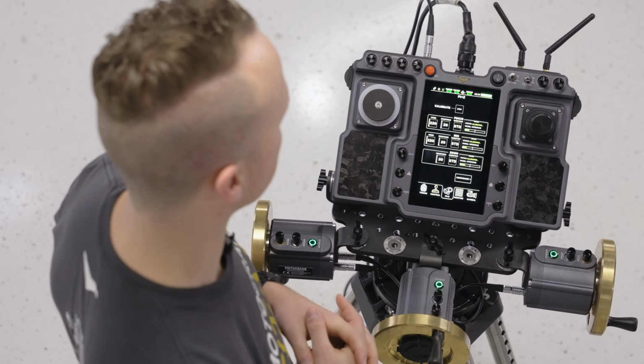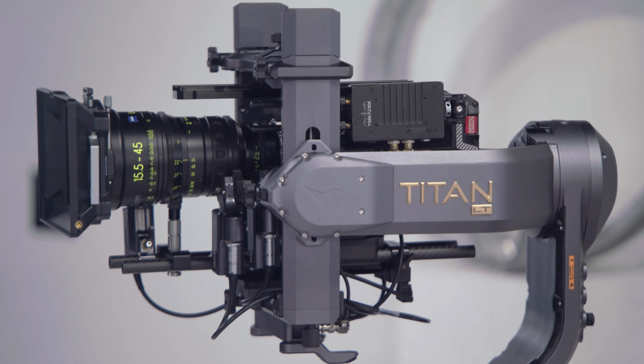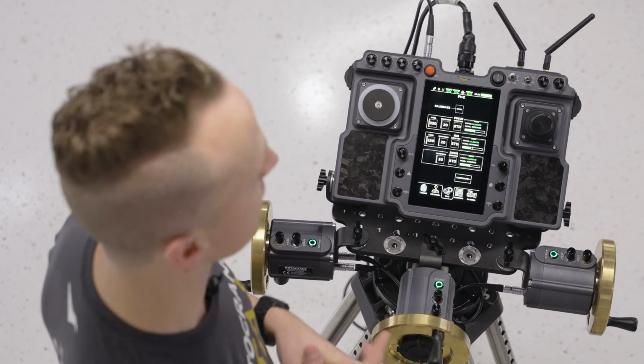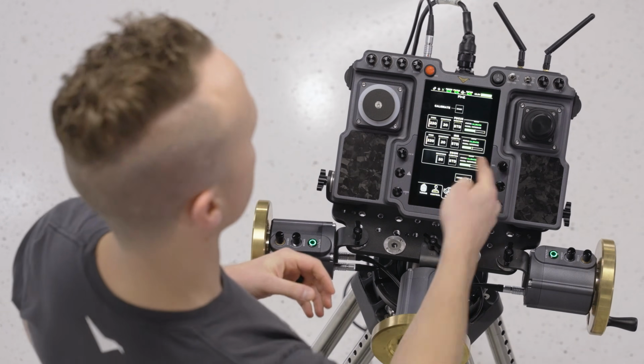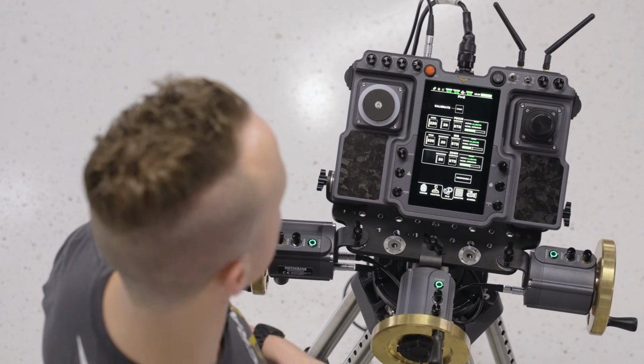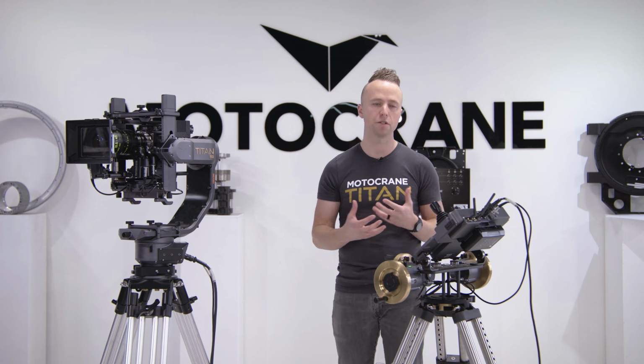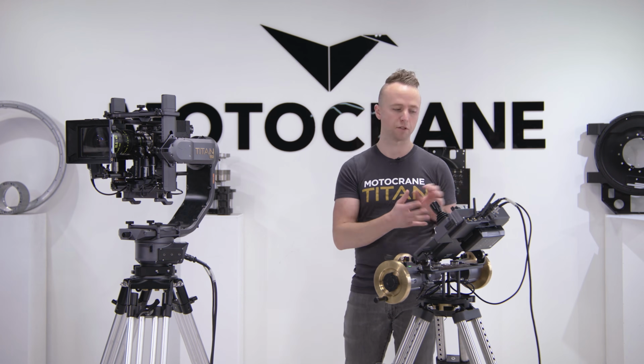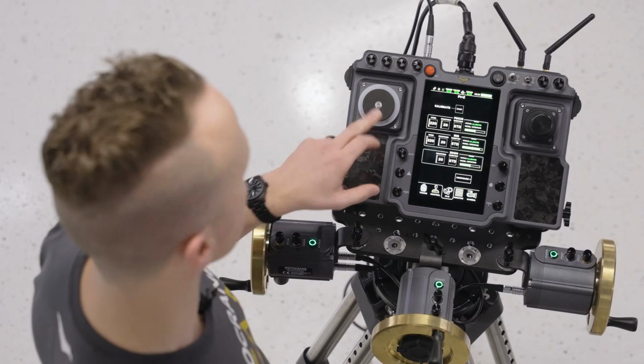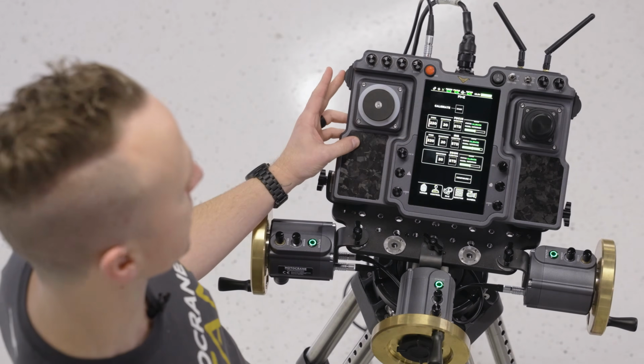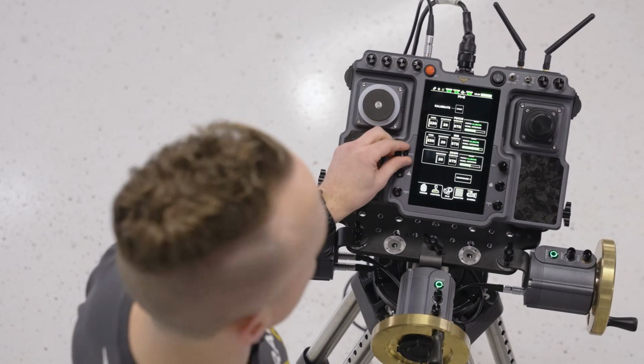So I'm just gonna simply press calibrate. You can see all three barrels of the lens rotating there and calibrating. And we have successful calibration on all three axes of the lens: focus, iris, and zoom. Now, the typical configuration for how you'd map focus, iris, and zoom on the controller is with focus here on this knob, zoom on this rocker joystick on the side, and then iris on this smaller pot here.